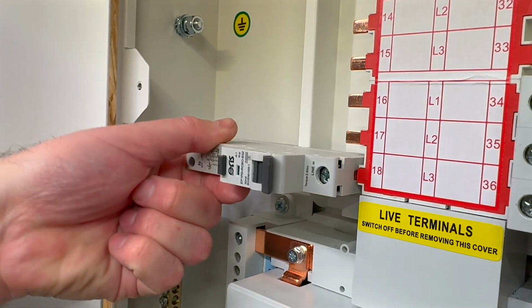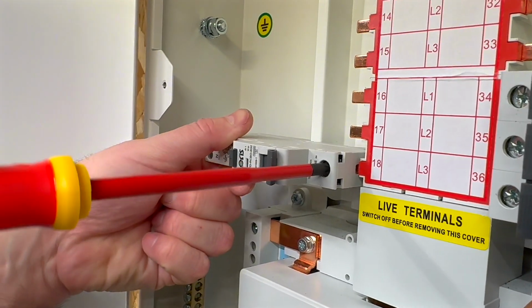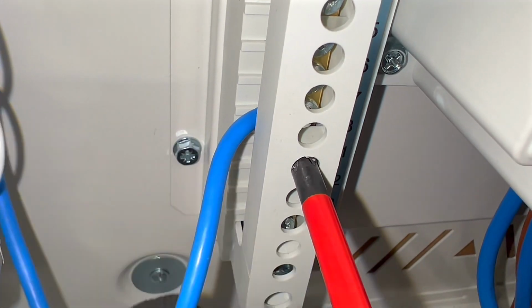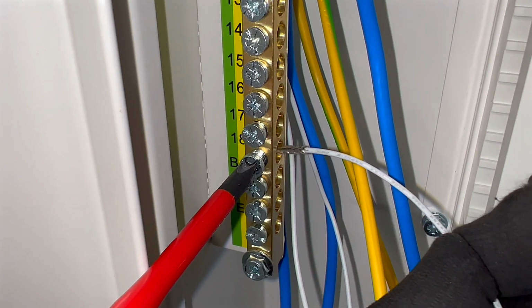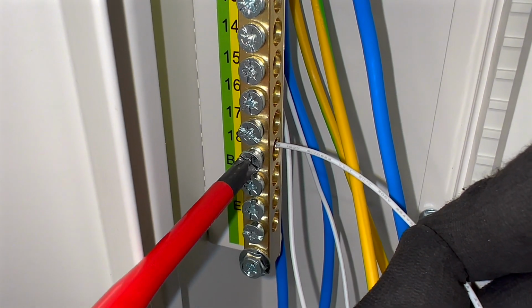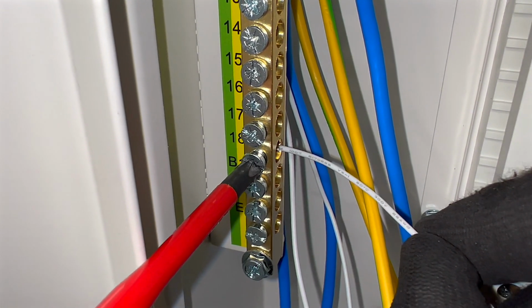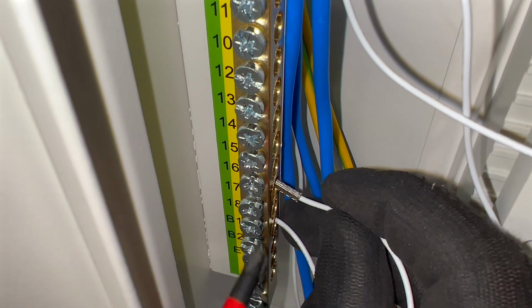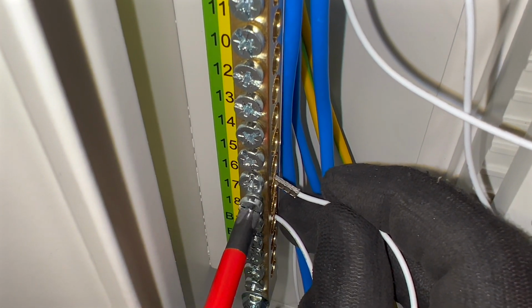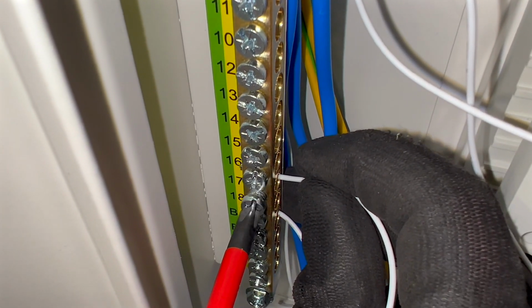RCBOs used in industrial boards generally resemble those found in residential consumer units. Featuring a flying lead for the neutral connection, many still rely on a functional earth, which must be connected to the earth bar. When installing RCBOs, it's important to carefully choose the circuit locations to ensure the flying lead is long enough to reach both the earth and neutral bars.